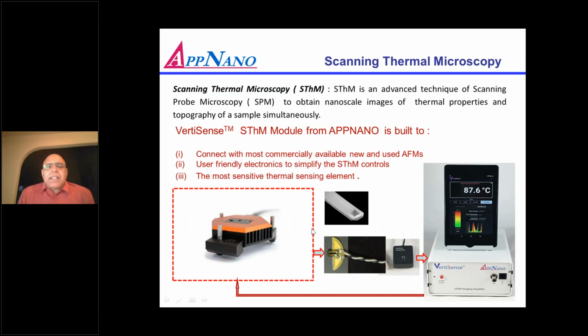All right, so the scanning thermal microscopy module is the system where you can do temperature mapping and topography simultaneously. This is done by a specialized probe. The probe should have a sensing element which can sense the thermal properties of the sample. These thermal properties can be sensed either by a thermistor or by a thermocouple, and there have been numerous types of probes in the past. There are only two which are in the market now, and I will show you what they are.